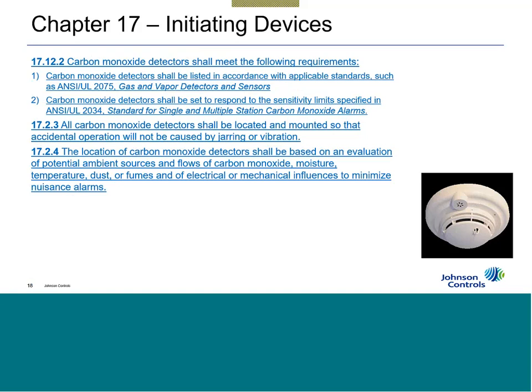Now, with Johnson Controls, the Autocall line, we have our cartridge in the base, and then you can have a smoke detector, and in some cases even a sounder base in conjunction with a CO device. And you could use this in an apartment or in a room, and if the carbon monoxide device sees an alarm, it can activate the sounder base of that device.